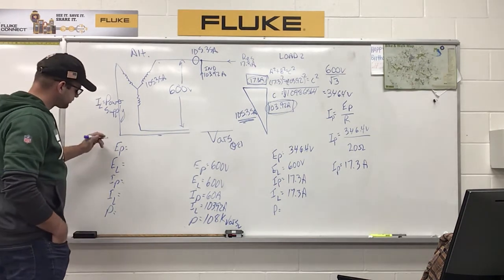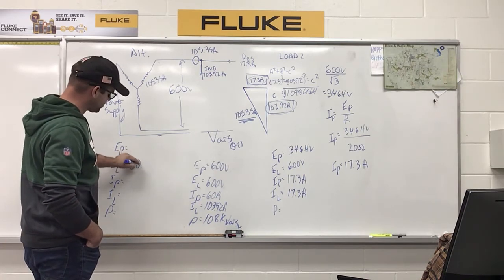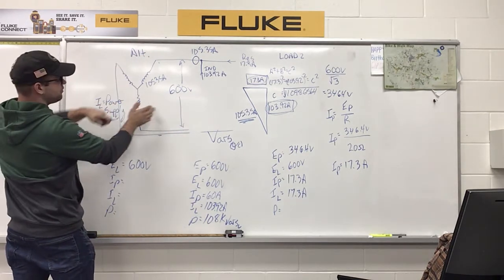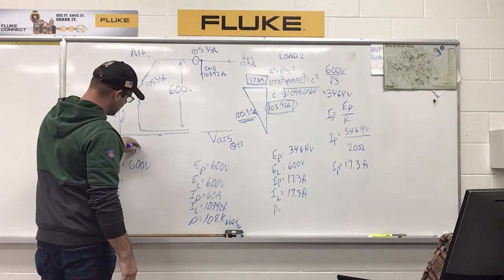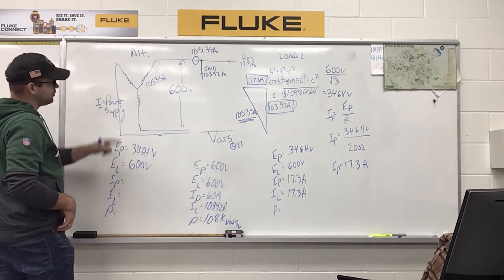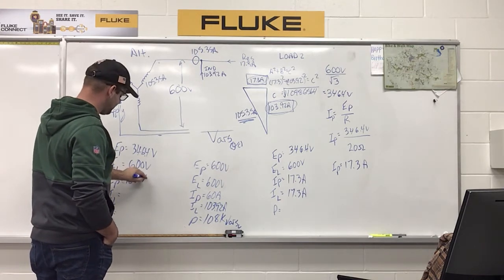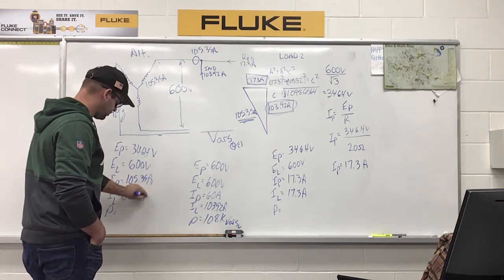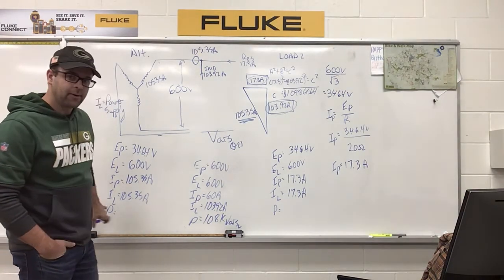All right, so our phase voltage. So let's start with line voltage, 600 volts. Remember, because this is in Y, we need to be √3 smaller because of what we talked about over there. So we have 346.4 volts. And we just established that our phase and line values are the same, 105.35 amps. And then is the question about the three-phase power.